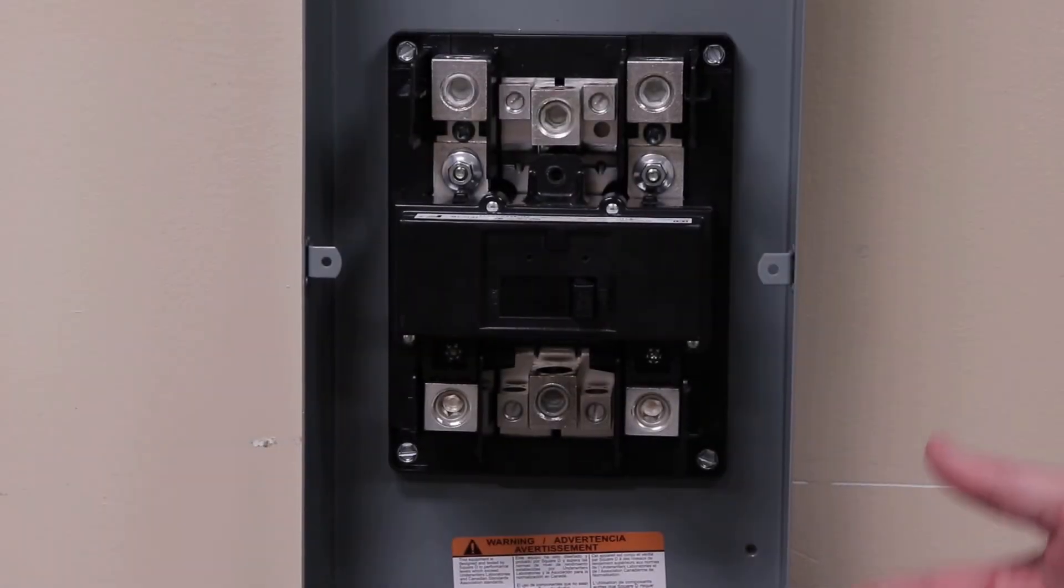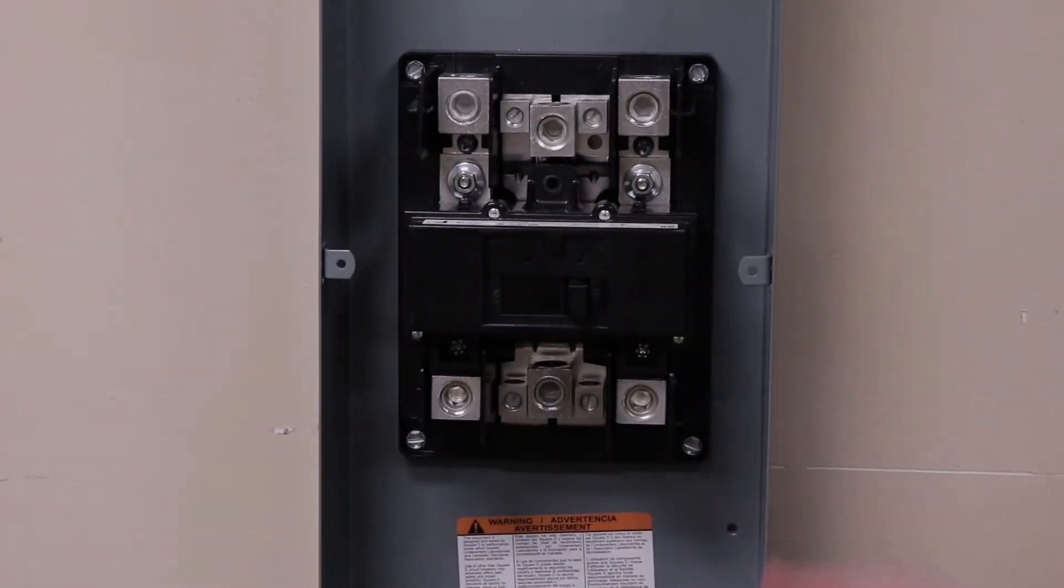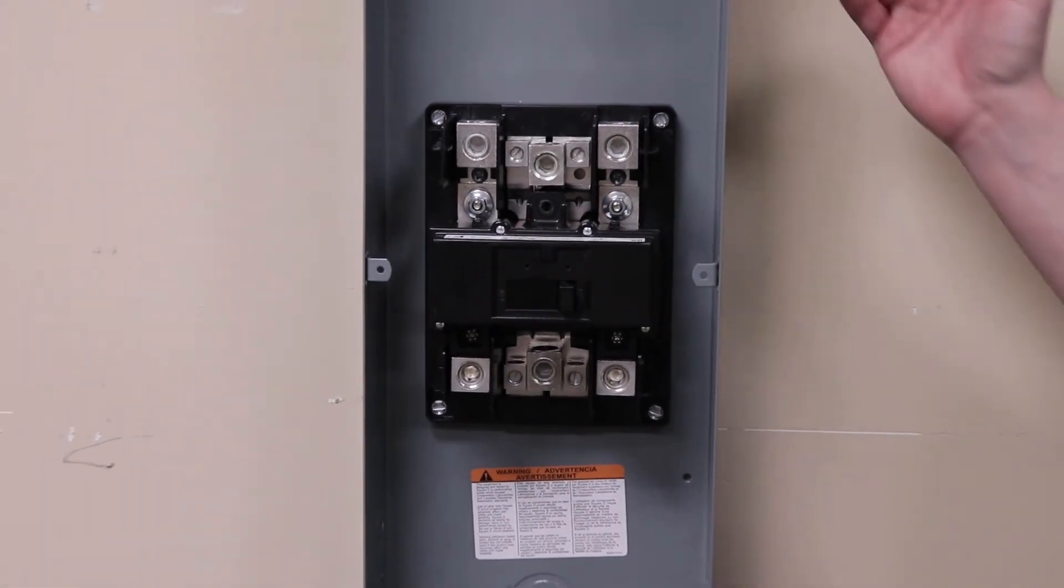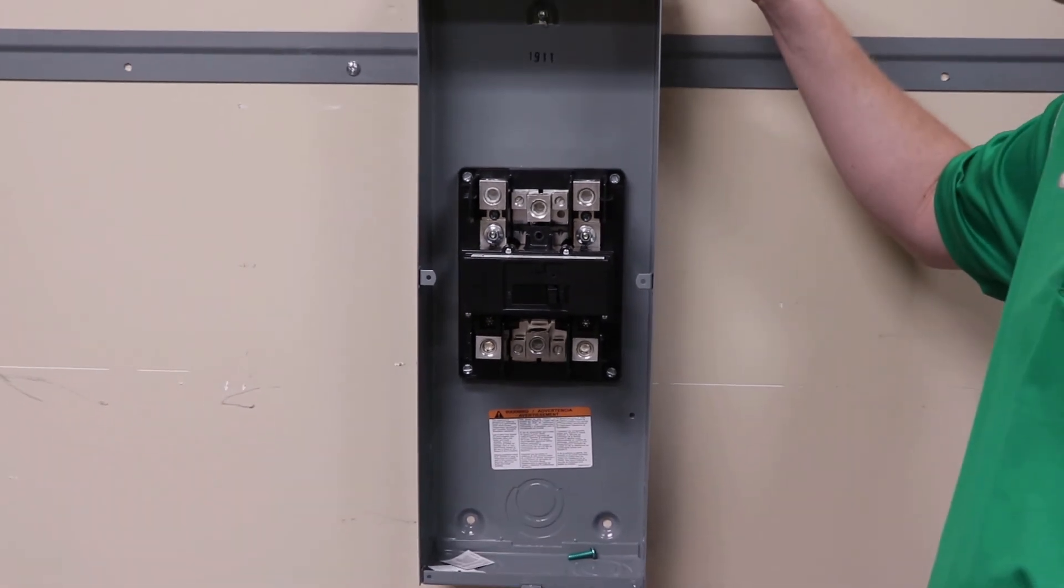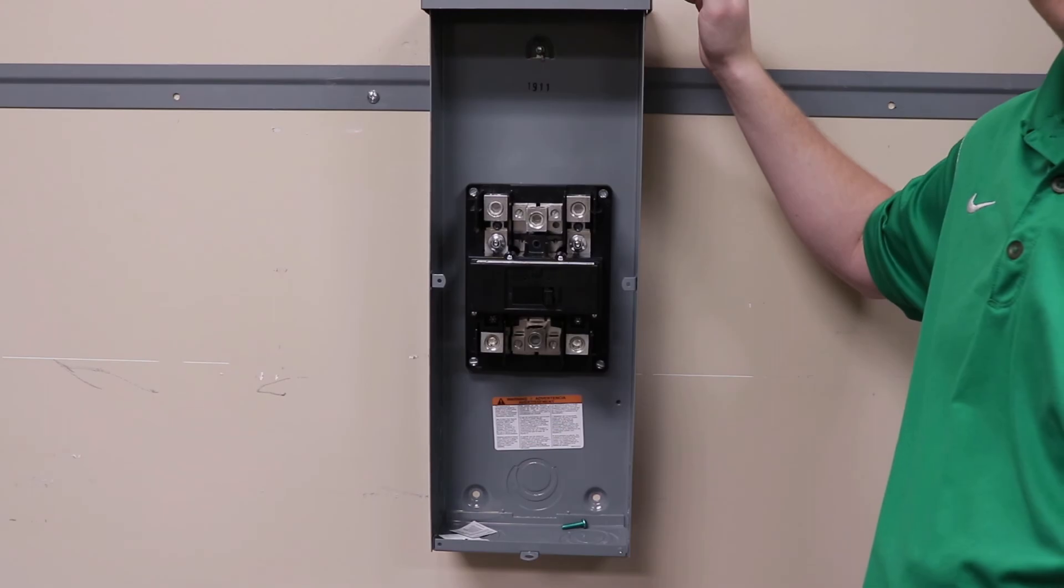There are no line or load markings anywhere on the enclosure or the wiring diagram, so you can come in with your source in either the bottom or from the top and take your load out of the opposite end.